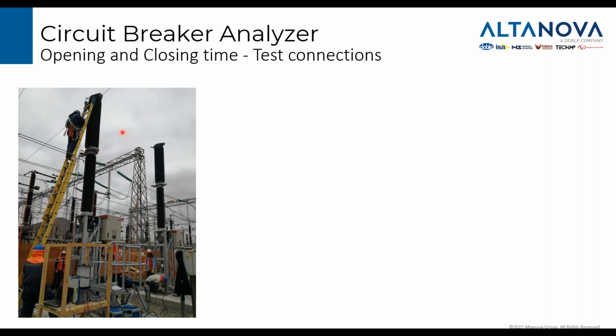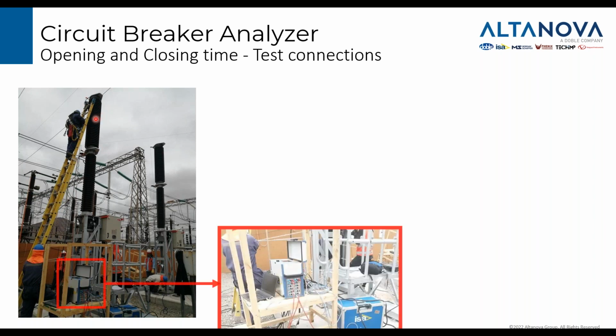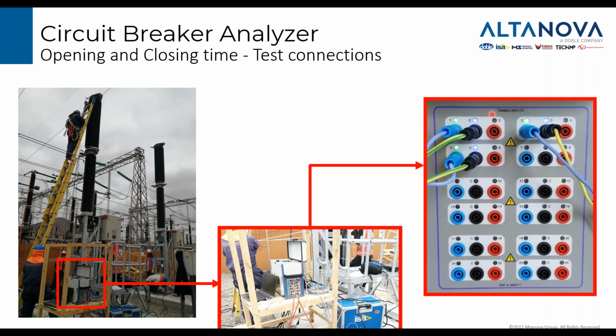The high voltage circuit breaker is a big device. So if you need to connect the clamps on top, typically you need a ladder or an elevator. The wires are connected to the timing input, and we can see here that on CBA 3000 there are LEDs that indicate the status. The green LED indicates open contact. In case the contact is closed, this LED becomes red. So you have an immediate feedback about the status of the breaks.